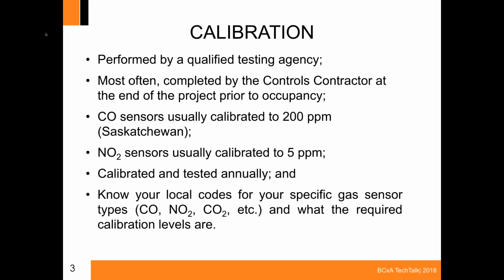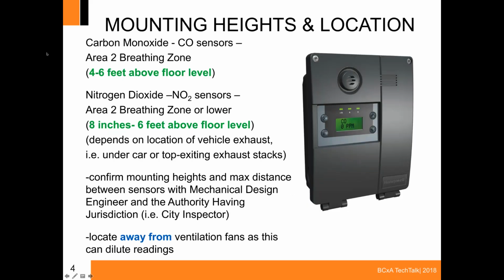So throughout this presentation, I may talk about a calibrated level, which is the 200 parts per million and 5 parts per million. I'll talk about a warning level, which will be less than that, as well as an alarm level as we get into the other slides. It's important to realize, though, that the 200 is a calibration only.